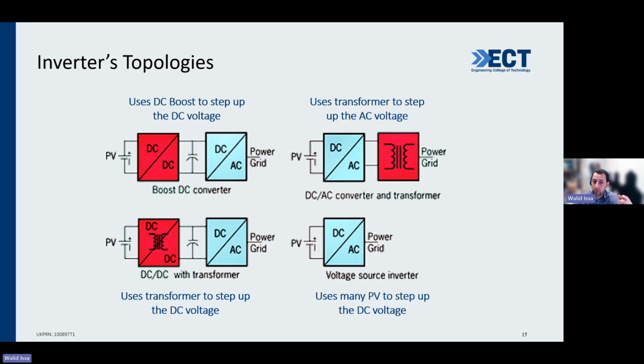The next one is a DC converter with a transformer, but different from the previous one. That one steps up or down at low frequency, 50 hertz. Here we have 200 volt stepped up to 800 volt, but using very high frequency pulsating, which makes the transformer the size of your hand instead of bulky like a room. So it converts 200 to maybe 700 volt, and then that's converted to AC by the inverter. So one is a low frequency transformer, the other is a high frequency transformer.